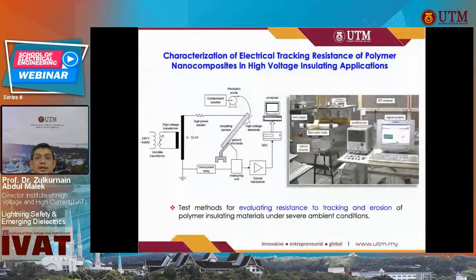Another important characteristic which we look into for new dielectrics is high tracking resistance. This is especially true if you want to minimize surface discharges and therefore damage to the insulation. So basically, we have two electrodes here. We put some liquid as well, and when the liquid dries, sparks will start to appear. And if the material is highly tracking resistant, it will prevent any carbonization, meaning to say we can develop material that is resistant to tracking.